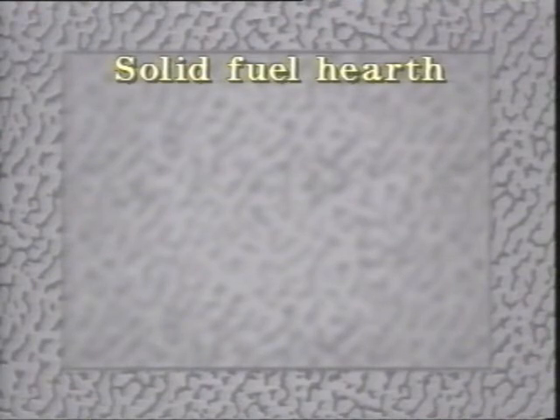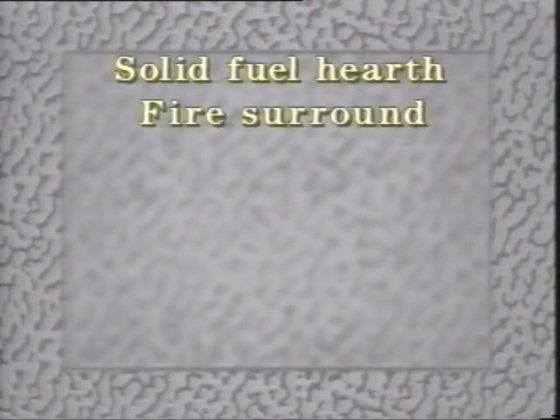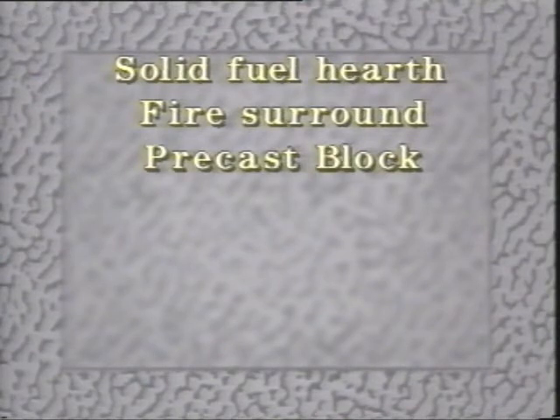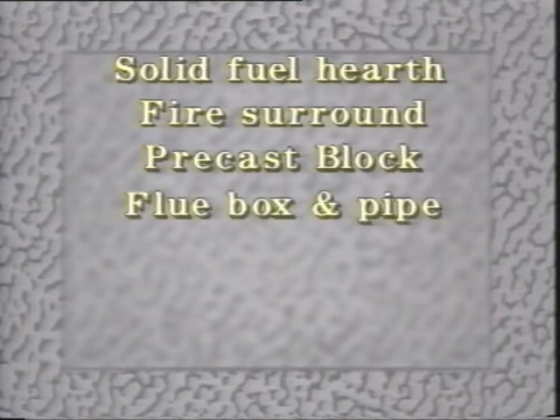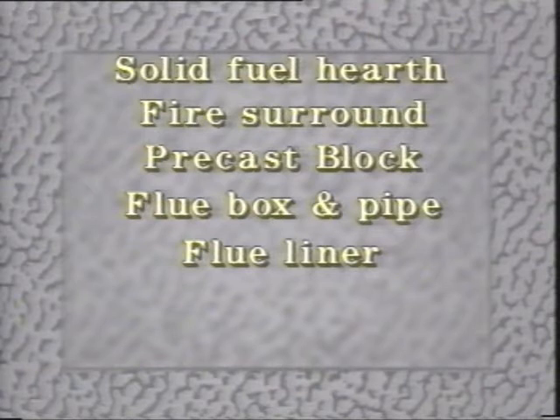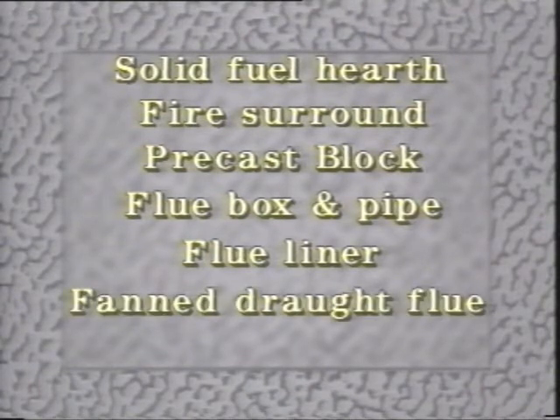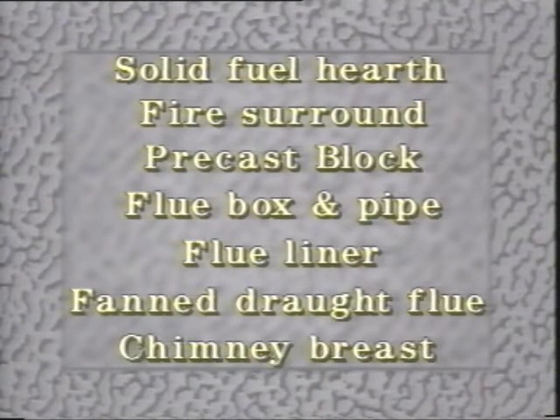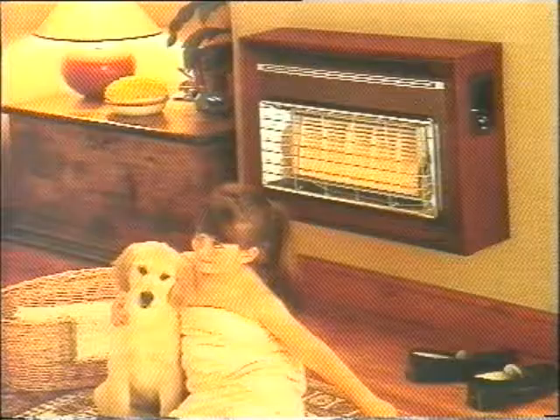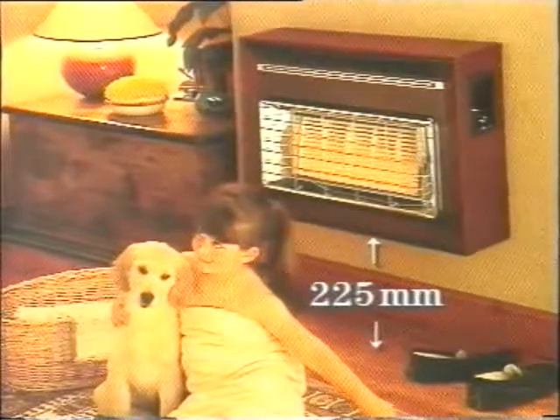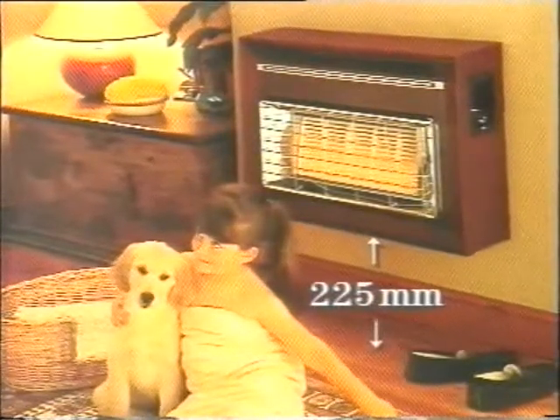This applies whether you're dealing with a chimney with a solid fuel hearth already there, a proprietary fire surround, a precast block chimney on a hearth, a flue box with a pipe, or using a flue liner in a chimney, a fan draft flue system, or an existing chimney breast with a wall on which the fire's mounted. With this last example, an added requirement is that the fire's flame and all its incandescent materials have got to be at least 225 millimeters above the floor covering.